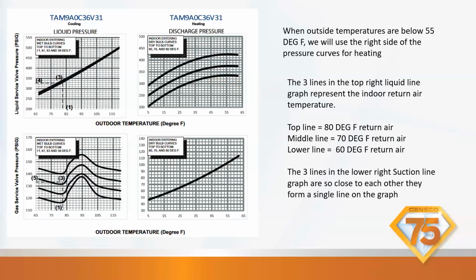And again, I like taking that return air temperature right at the filter box, right? Because you may have 2 to 5 returns in the house. And if you're just taking it at the upstairs one, you're not getting a correct reading. Also, detecting the temperature at the return air at the unit, what's actually going into the unit, you can detect to see if there's maybe a makeup air damper that's stuck open, pulling in 30-degree air.